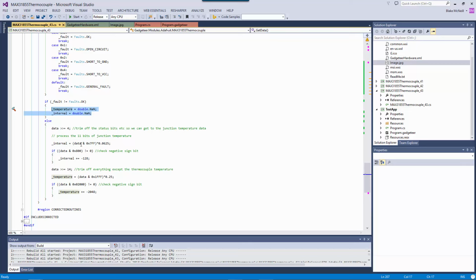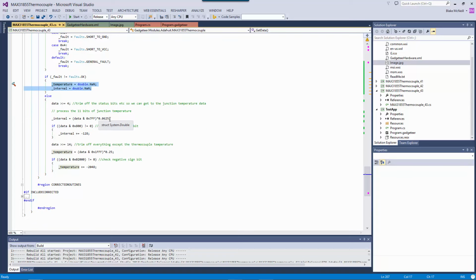That gets us into the internal temperature, which is 11 bits of information. We take that number and multiply it by 0.0625, and that gives us the internal temperature. Now we do have to check to see if it's a negative number or not.